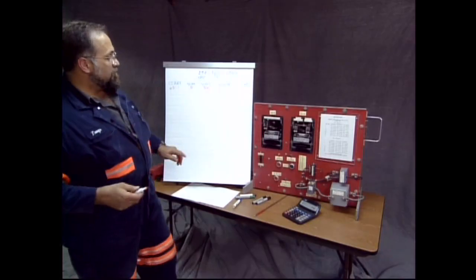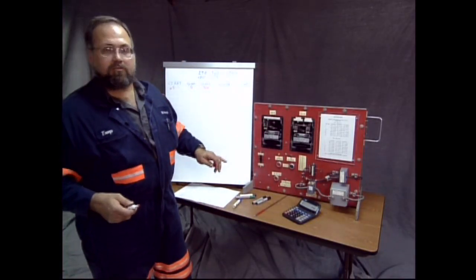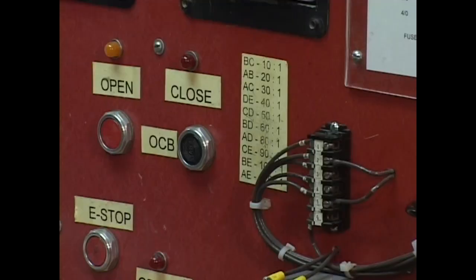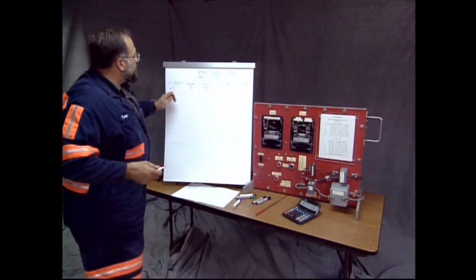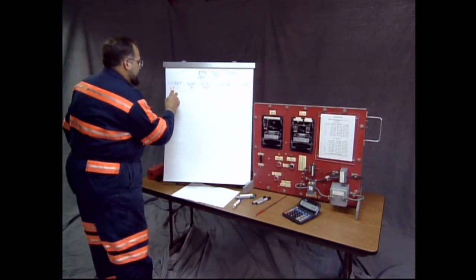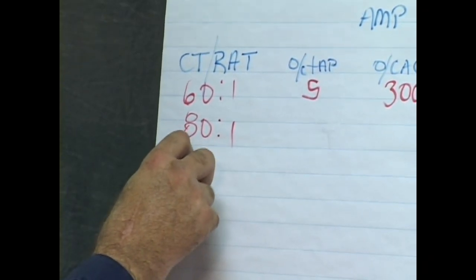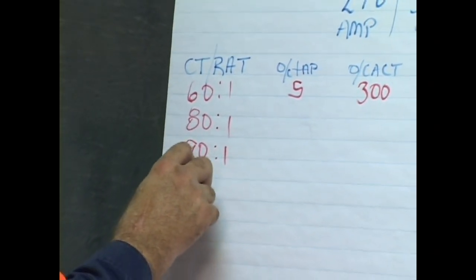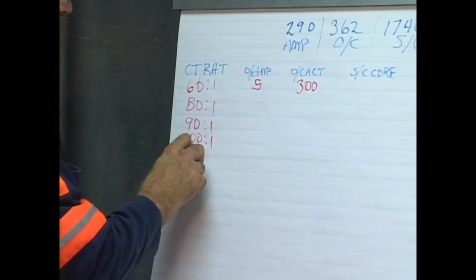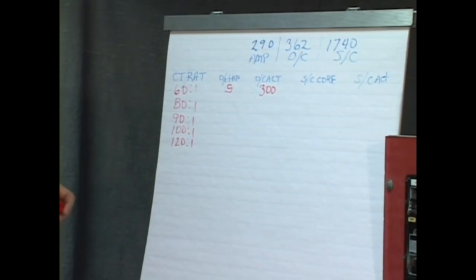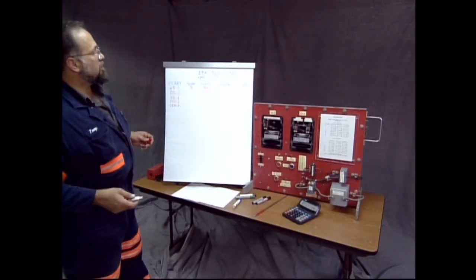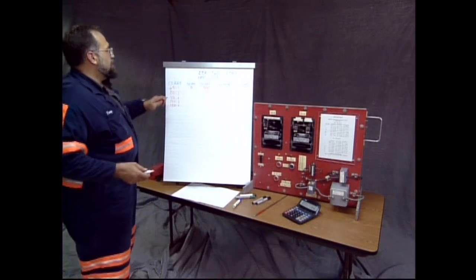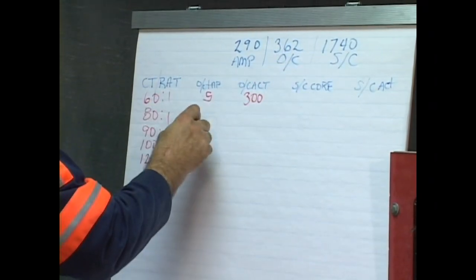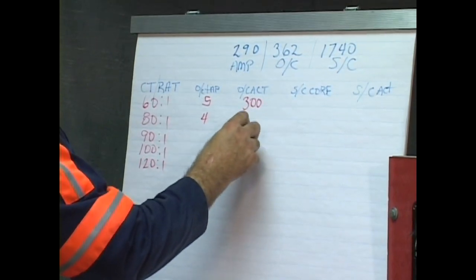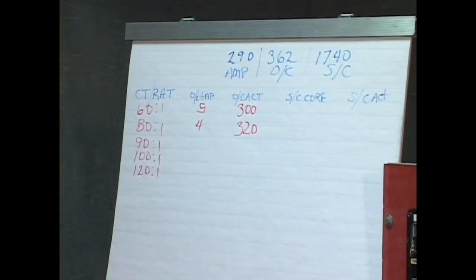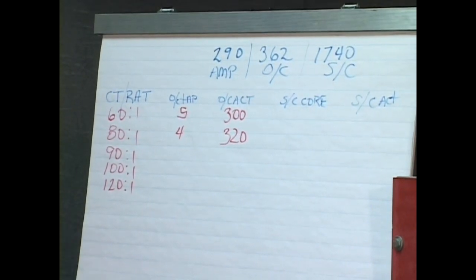Now after you determine that with a tap of 5, the largest CT that you could have with a tap of 5 is 60, then it would be safe to go ahead and list all the other CTs under this, such as 80, that's your next one, 90, 100, and 120. That's all your available options for this particular cable. So let's have a look on this. If we chose an 80 to 1, we would divide the 362 by 80. That would give us a tap of 4, an overcurrent value of 320. Well, that's better than the 300. That's closer, not necessarily better, but it's closer to our maximum.